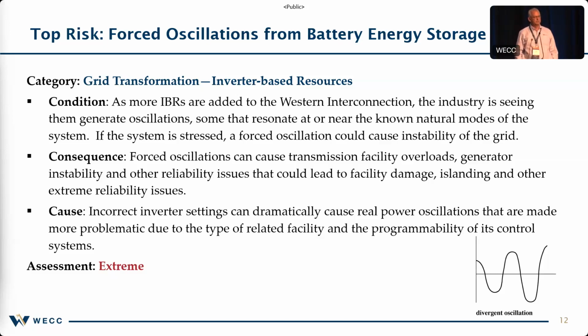What's really interesting about a battery versus a normal PV plant is if you ever worked in a power plant, a PV facility is fundamentally wide open. The valve's wide open, there's really not a lot of control interaction at a PV plant. If the sun's up, you're going to produce megawatts; when the sun goes down, you don't. A battery is the complete opposite. Not only do you get to control it whenever you want, you get to charge it whenever you want also. And when I say you, I'm talking about the generator owner.